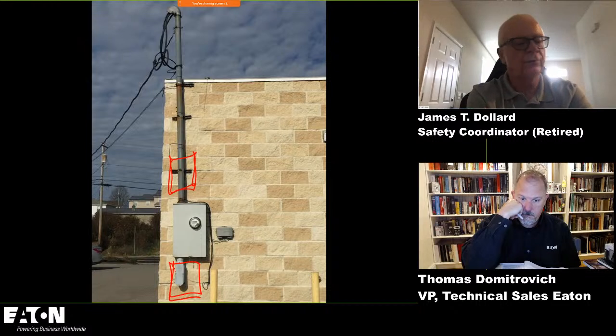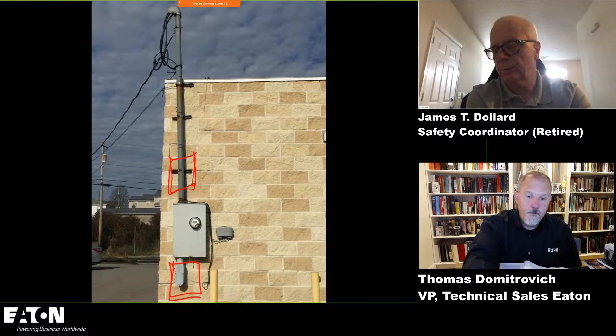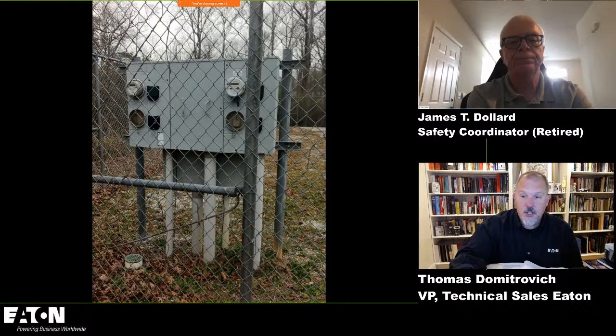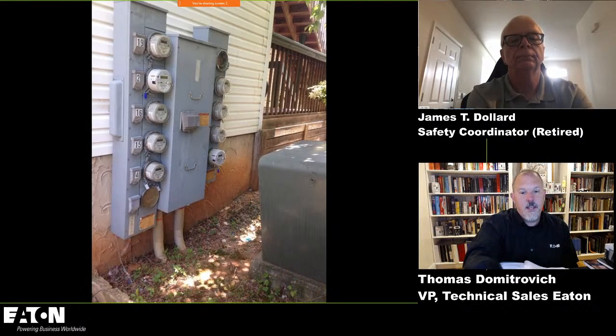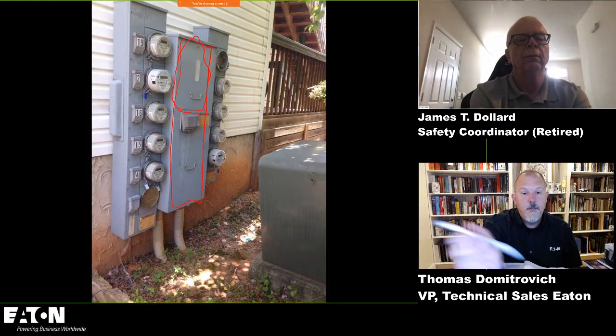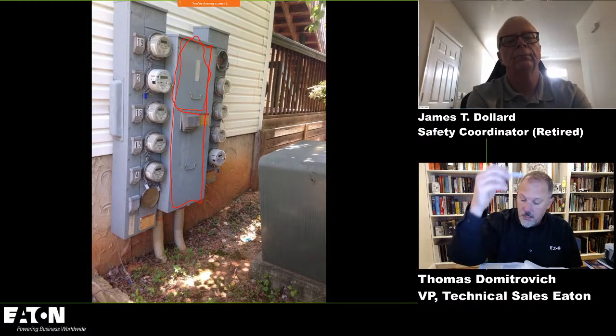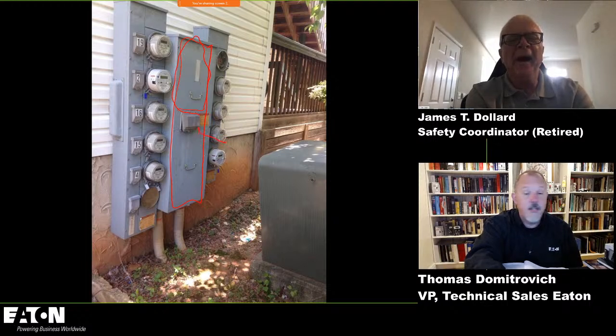Right, and the easiest way to do it is to just buy a meter housing that has a side compartment with a 1 pole or 2 pole, and you're done. Yeah, good point. And then that's just another meter center that has that same issue. And there's another one. So I just threw some images in. Now you have one like this. The main breaker, I believe this center cavity has that main overcurrent device. Yeah, that's going to be a main in there. And then you would have to barrier off the line side based upon the barrier requirements. And then this would meet the emergency disconnect. This would have to be labeled as an emergency disconnect. They might have some workspace issues on that right side there. Oh, yeah, because of the transformer. Yep.